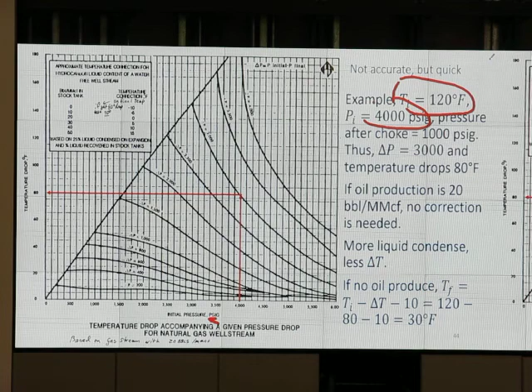Let's take a look at this. The previous one is just for methane, right? But if you don't have pure methane, you have something else, we may use this one. We have a temperature of 120 F and an inlet pressure of 4,000 PSIG. This chart uses PSIG, so I changed to PSIG, but PSIA is about the same at very high pressure. I start from 4,000 PSIG, and I know the outlet pressure will be 1,000. 4,000 minus 1,000 equals 3,000.